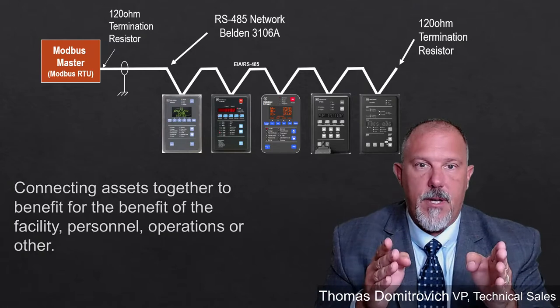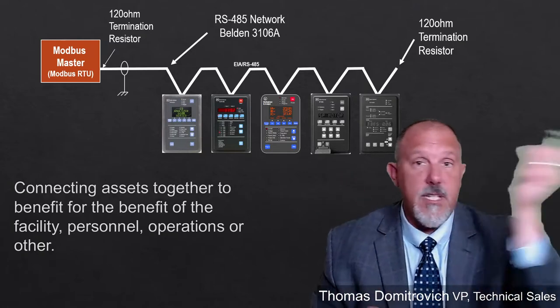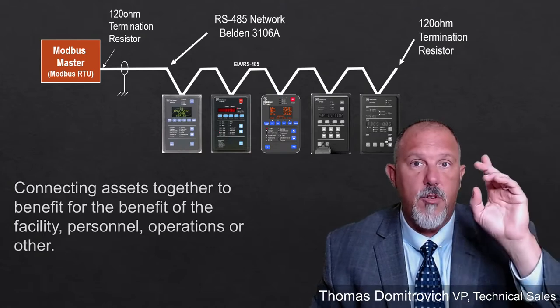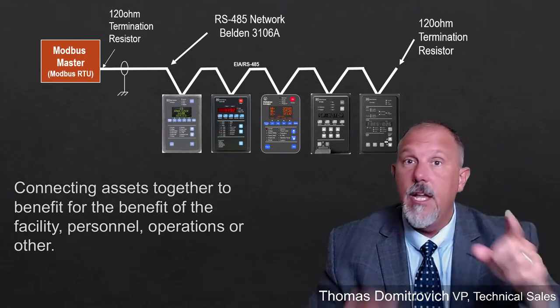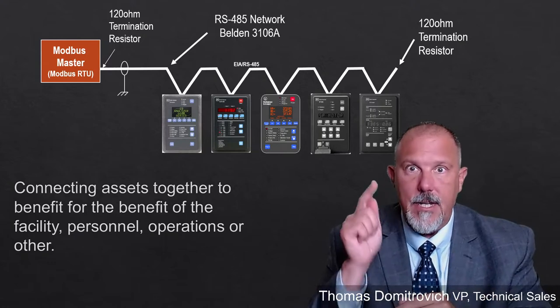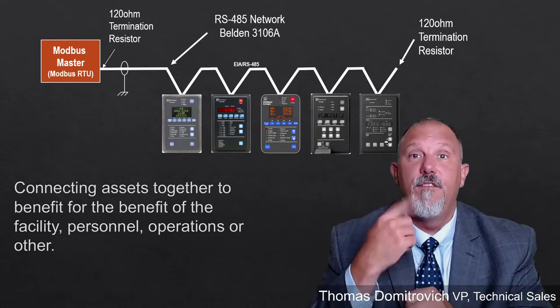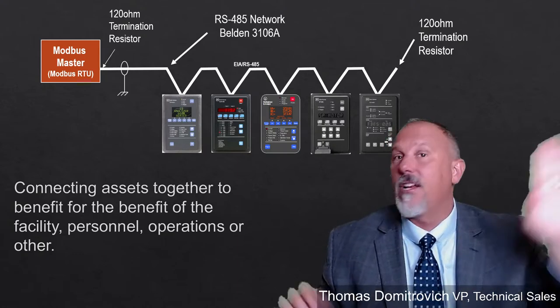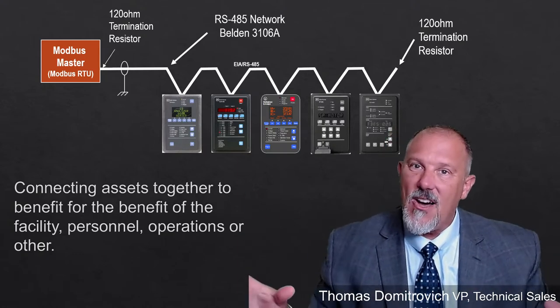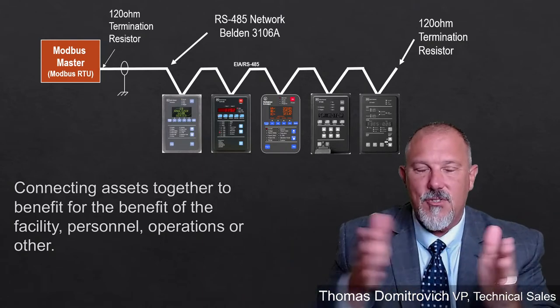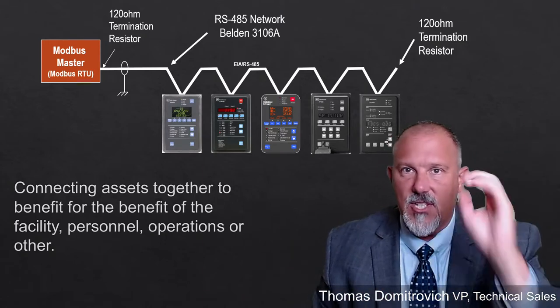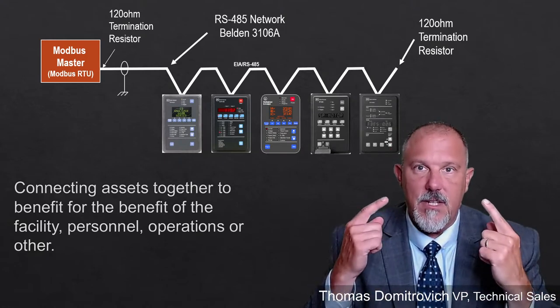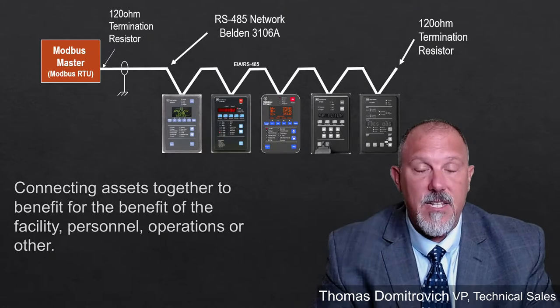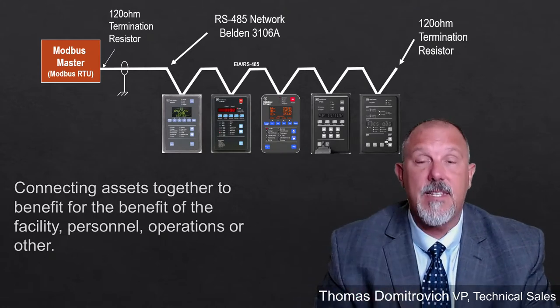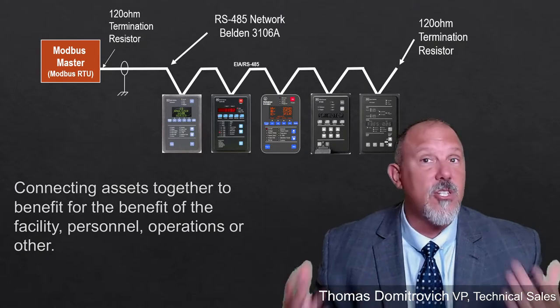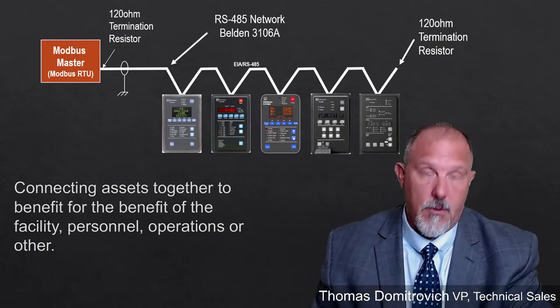And if you understand Modbus and you're a device hanging on the Modbus network, you're listening to all the messages and interpreting all the information. The moment you see your address, you're going to go, this is for me. You're going to take that message out and read it. You're going to say, okay, I know you want voltage. You're going to grab voltage and send a message back. No one else is going to send a message. No one else can talk in this master-slave type of environment, where you have a Modbus master that's sending a message out, and each of these devices has to listen. Only the device you are addressing is supposed to respond. Only one device at any time. You can't have the other devices just talking out of turn. That's following the protocols.